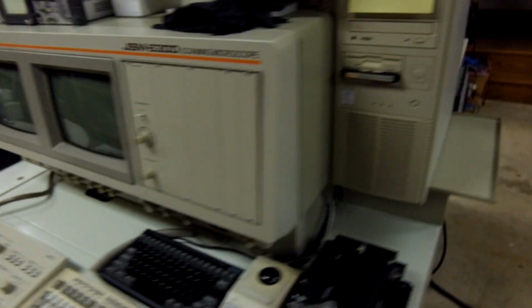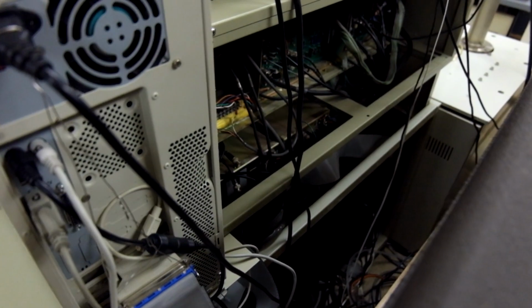Around back of the console, you'll see all the wires and everything I had to connect to get this thing running. There's a ton of unlabeled and crazy cables, and luckily I had a wiring diagram, so I was able to figure out what different circuit boards and things do. But it really is a rat's nest back here. This is the 30 kV power supply for the filament. There's a high tension cable that comes out of it, and this is all immersed in transformer oil. I had to replace that. That was fun.